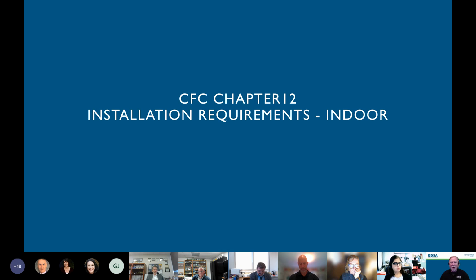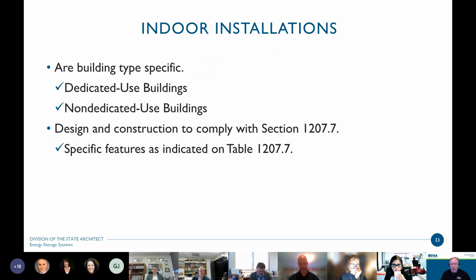So, some indoor requirements. Real quick through this because I want to focus more on the outdoor. When we talk about indoor installations, there are two types of buildings per code. They're considered dedicated use buildings or non-dedicated use buildings. The terminology is pretty self-explanatory. If a dedicated use building isn't going to have anything in it other than your battery storage equipment, there may be a small area, code will permit 10% or less of the floor area, for some kind of an office or something to be there. But generally dedicated is pretty focused.